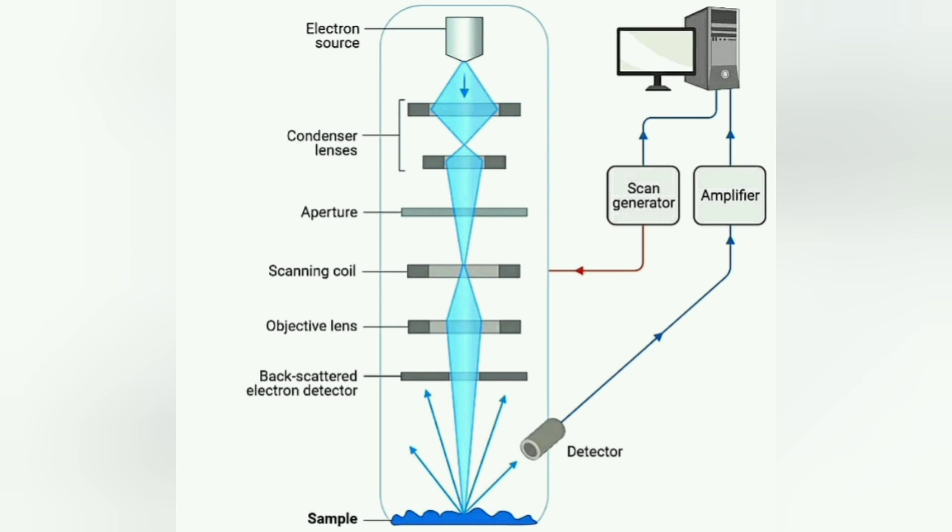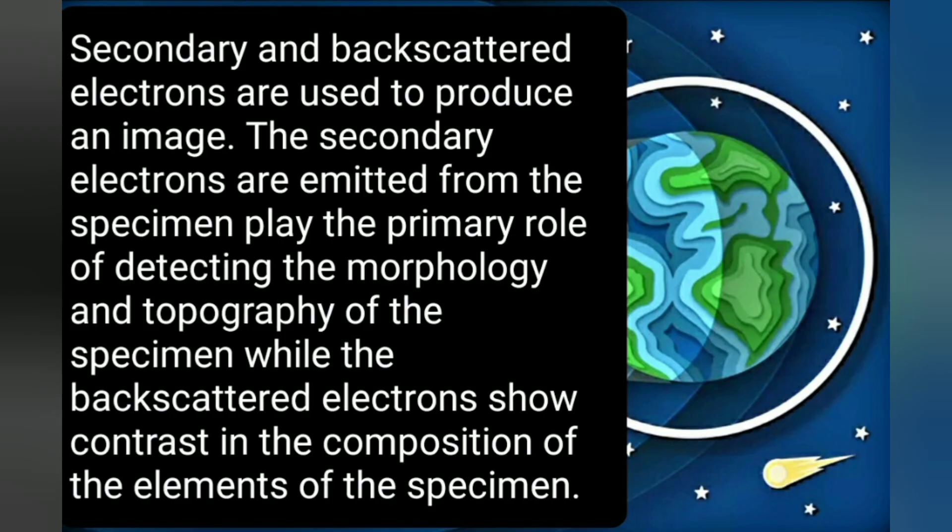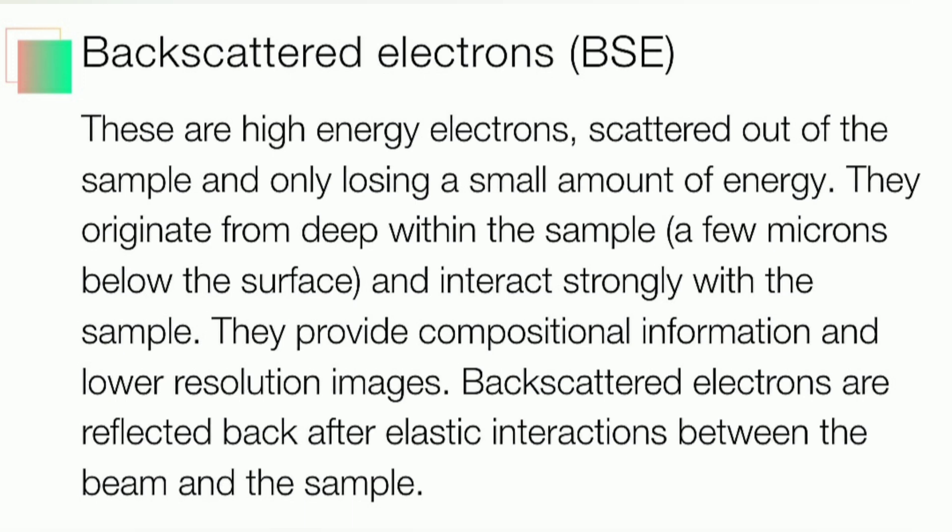We will learn about certain different terms like backscattered electrons and secondary electrons. These two terms are important. Backscattered electrons are high energy electrons scattered out of the sample and only losing a small amount of energy. They originate from deep within the sample and interact strongly with the sample. They provide compositional information and lower resolution images. These electrons are reflected back after elastic interaction between the beam and the sample.